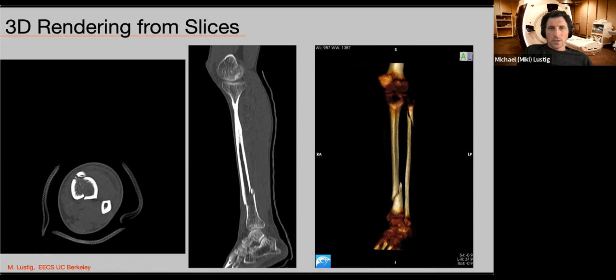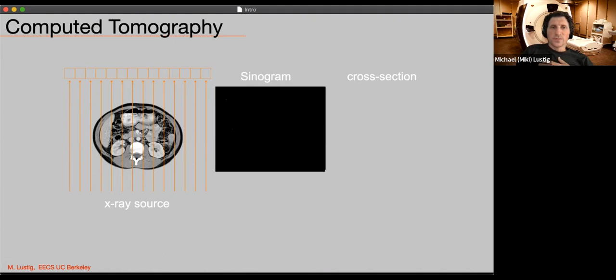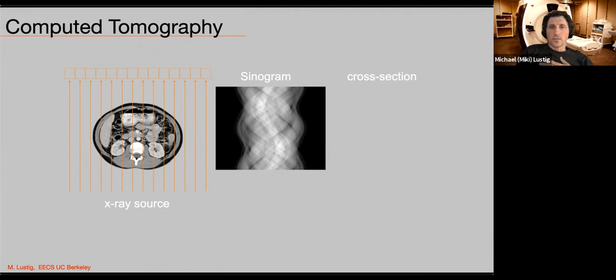All right. So this is all about what's called filtered back projection. The idea here is that you have some X-ray source that shines through some object, and you have a detector, and whatever is shown on the detector is pretty much a shadow of that object. As you go around, the shadow changes, and that provides you enough information to take what's called a sinogram, perform a filtered back projection, which we'll be covering somewhat in your class, and then reconstruct the slice from this. There's just enough information there to be able to do that.